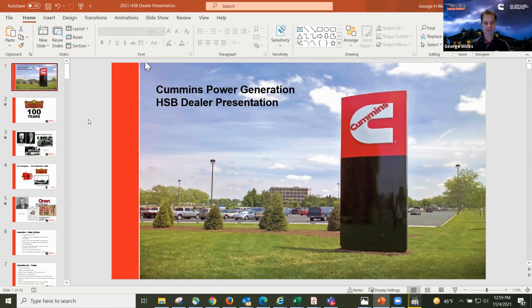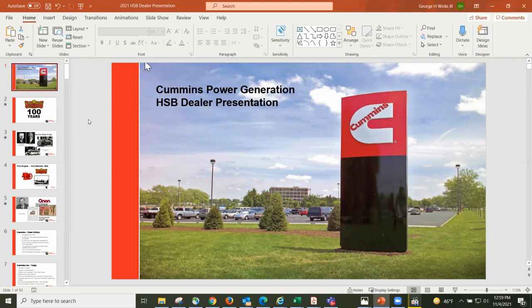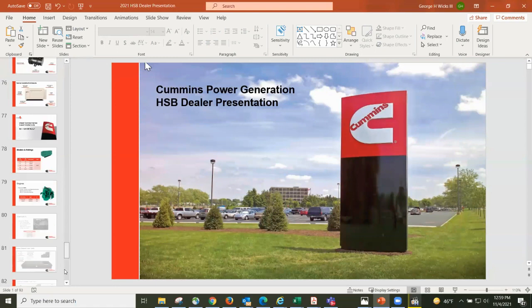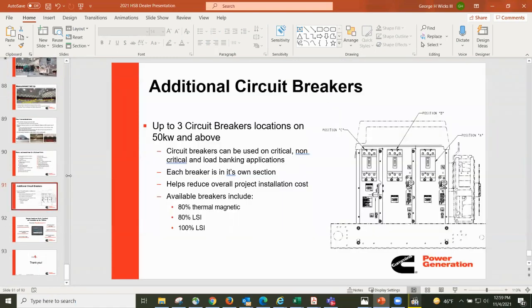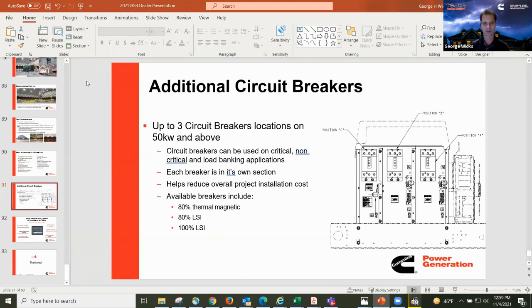Yes. And all of your generators, and you had a slide there that showed one generator set, more of a commercial or larger industrial, that had 3 circuit breakers there. Could you get that slide back? Yeah, that's the one. Right. Yep. What's the rating of those breakers? So that's our picture of our 45 to 100 kW, the circuit breaker base. So they're going to have one breaker. The standard unit out of our factory is built to the voltage, whether it's 240 single phase, 208 3 phase, and it's going to have one main circuit breaker, and that's sized by the factory over the rating that the generator is rated at. So if our 100 kilowatt has a 350 amp capacity, the factory is going to oversize that breaker to maybe 400 amps.